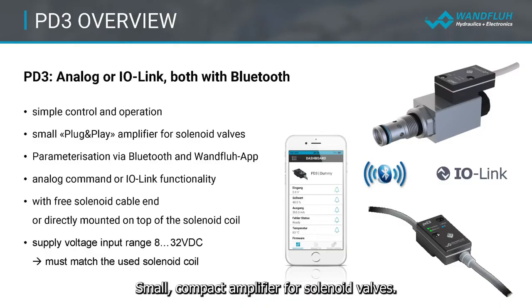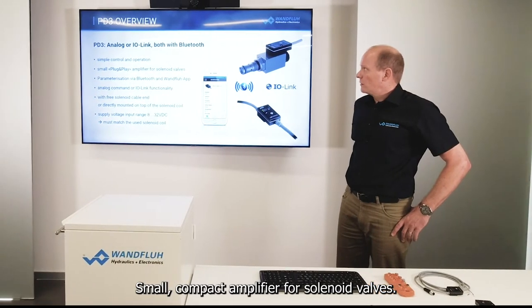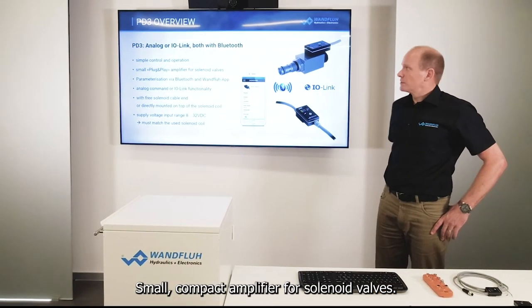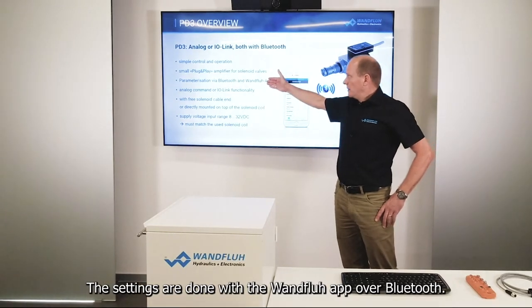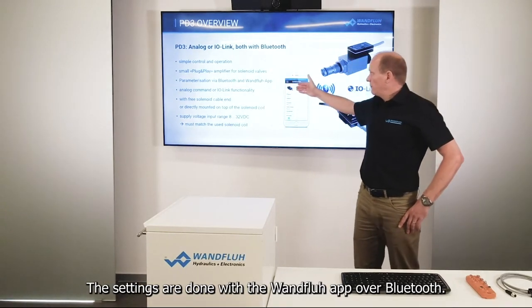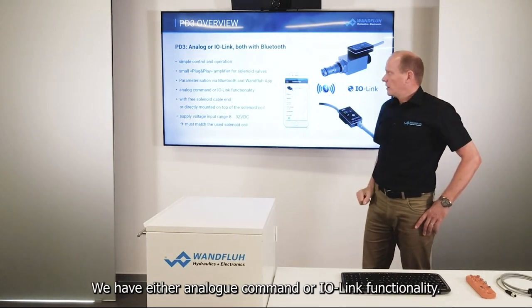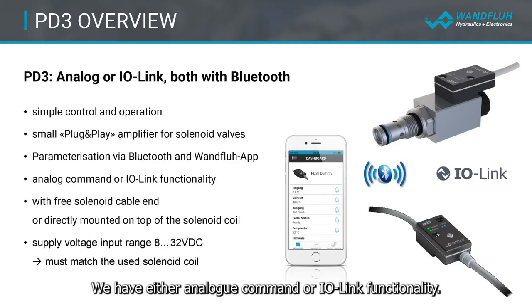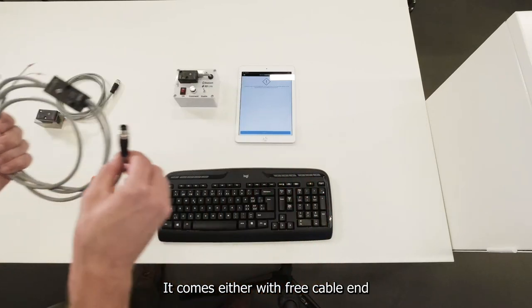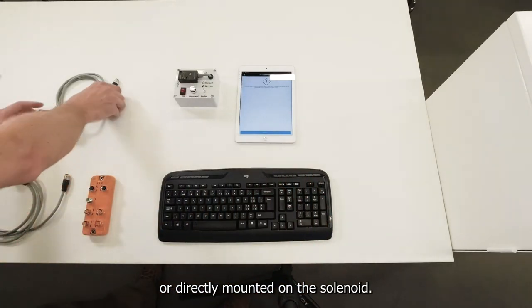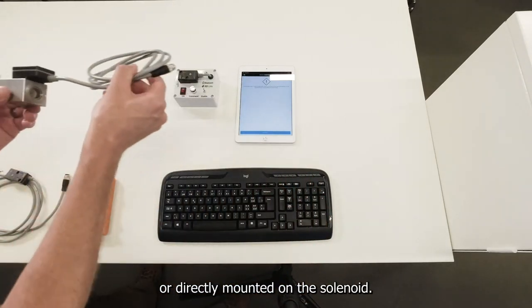The PD3 offers the following functionality. It's a small compact amplifier for solenoid valves. The settings are done with the Wandfluh app over Bluetooth. We have either the analog command or the IO-Link functionality. It comes either with a free cable end or directly assembled on top of the solenoid.